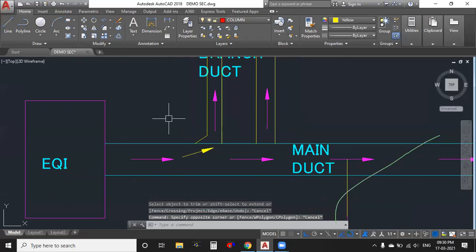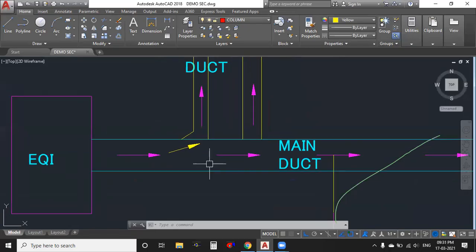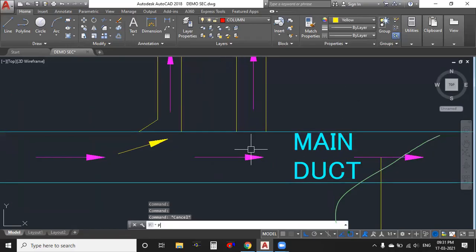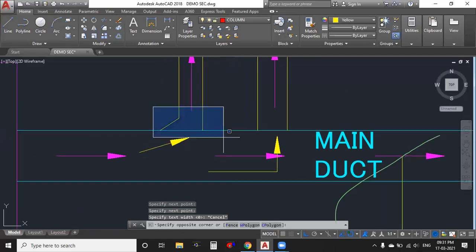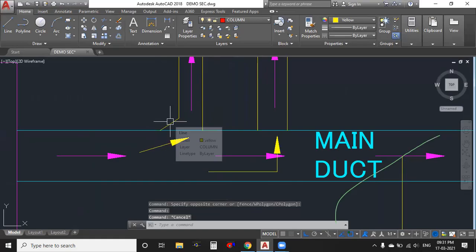Of these two ducts, which one will air enter easily? The 45-degree angle, right? Air and water don't have any shape or size; we can find them only in a straight path, and they won't take any direction. Air goes in a straight manner, and if you want it to take a turn, you need to guide it. If you are not maintaining any shoe neck, air will enter at a 90-degree angle. If you maintain a shoe neck, it stands at a 45-degree angle and air will enter the duct easily.